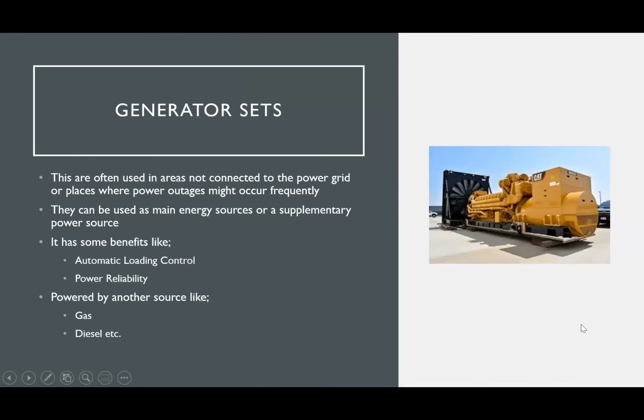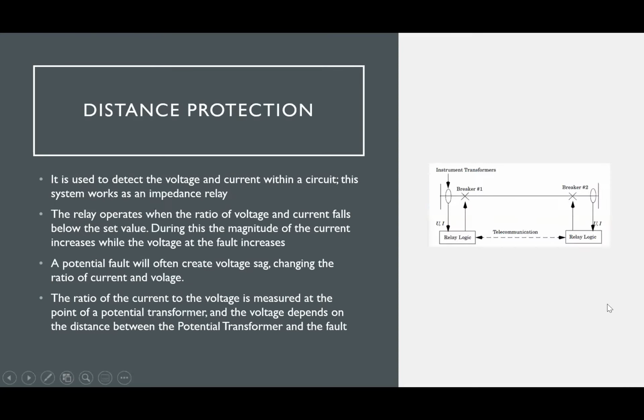And here we have generator sets. These are often used in areas not connected to the power grid or places where power outages might occur frequently, like a third world country or a facility that is just off the grid. They can be used as main energy sources or a supplementary power source. It has some benefits like automatic loading control and power reliability, and it's also powered by other sources like gas, diesel, natural gas, etc. And here we have distance protection.